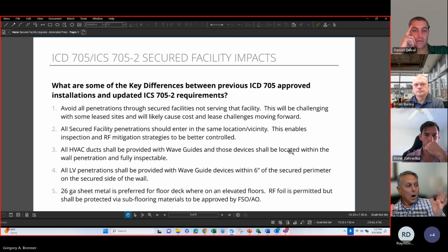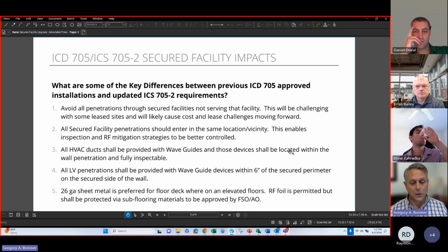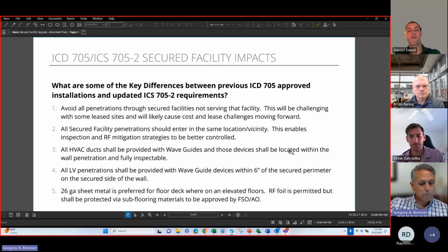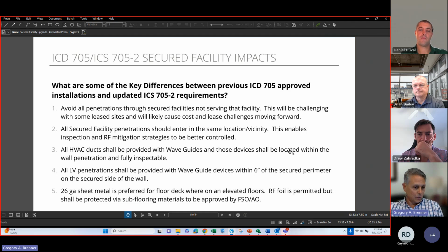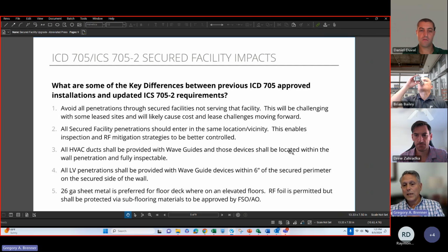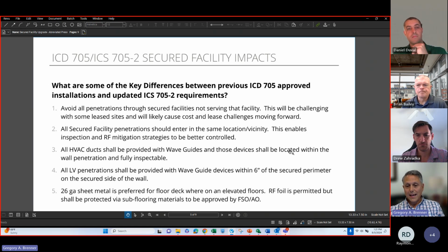So all secured facility penetrations should enter in the same location and vicinity. So you have a four-sided room—we're designing for our incoming electrical, mechanical ductwork, and any other penetrations to come in on the same wall, if you can, within the same 10 feet of that wall. The accrediting officers want to be able to go to a single wall and inspect, not have penetrations around the entire room, even if they are RF mitigated. They want it all in one location where we can do it. That's something that hadn't been enforced previously.